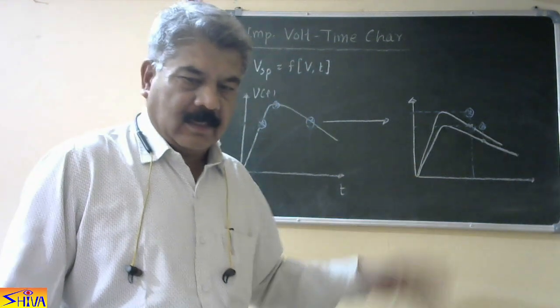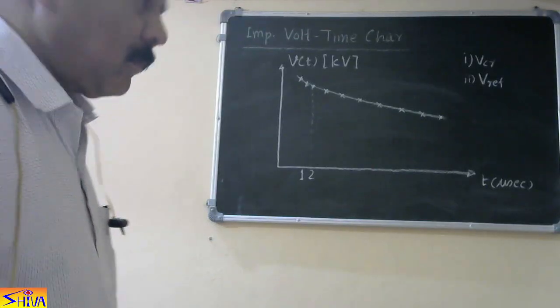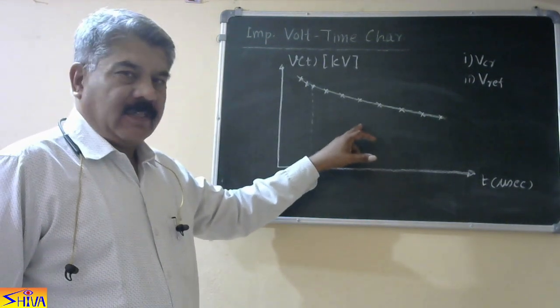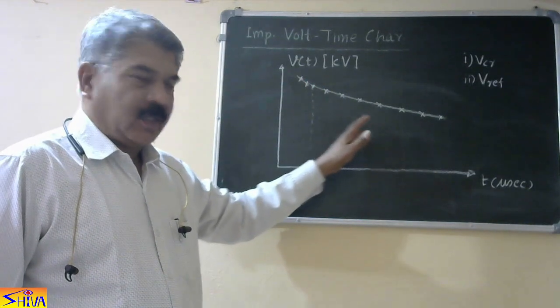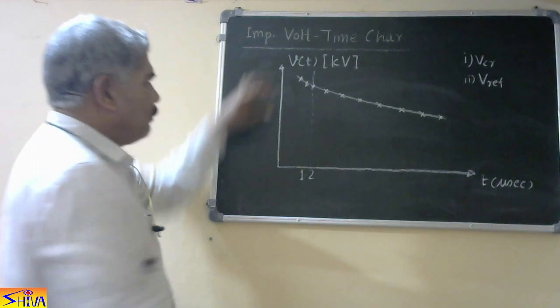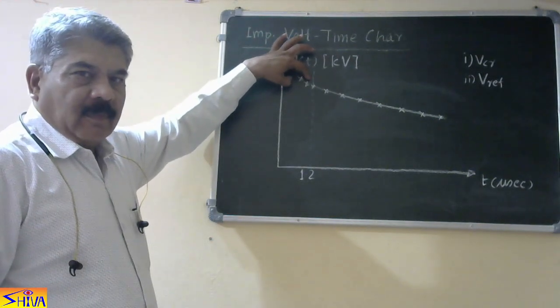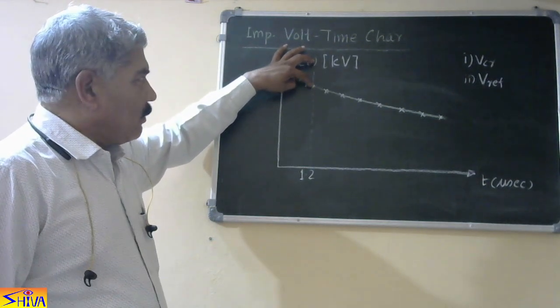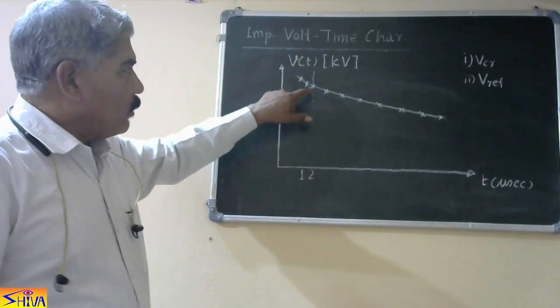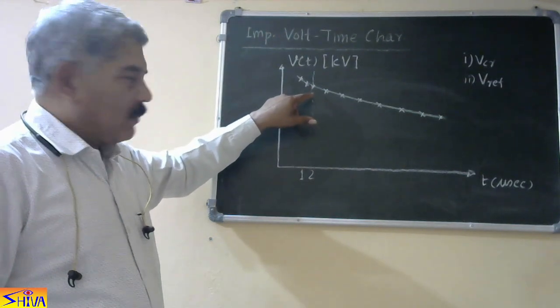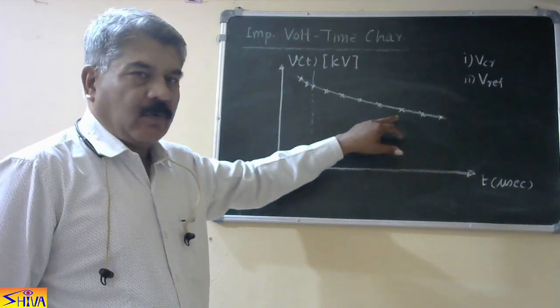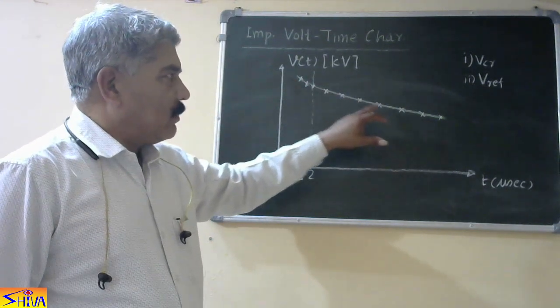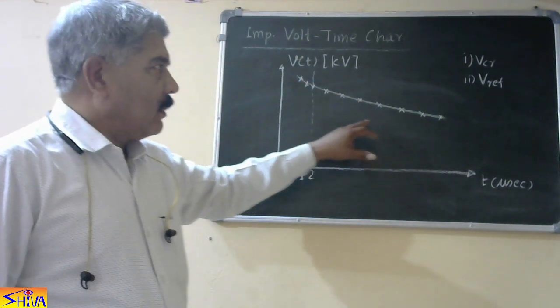The volt-time characteristic will look like this. We obtain different points and join them by a smooth curve. Two points show that spark over has occurred on the wave front. One point shows that spark over has occurred at the peak value — at 1.2 microseconds. All the remaining points show that spark over has occurred on the wave tail. So this is the impulse volt-time characteristic.